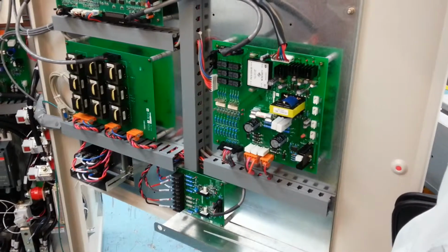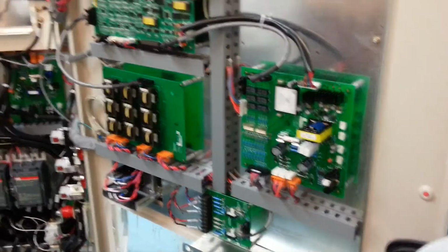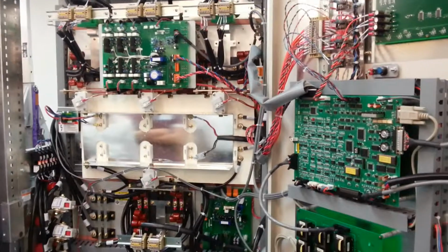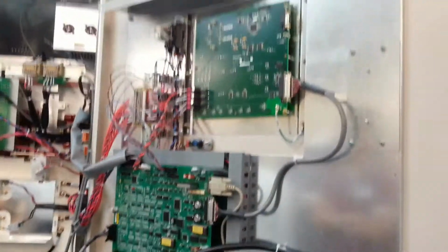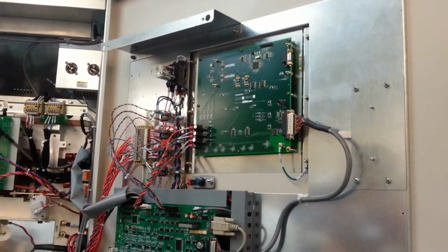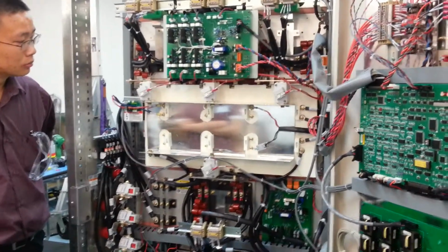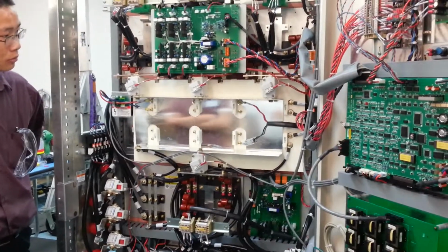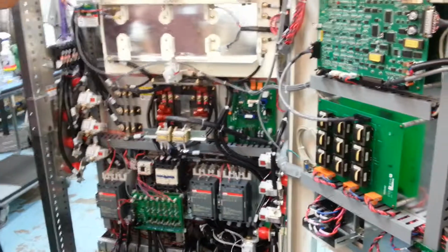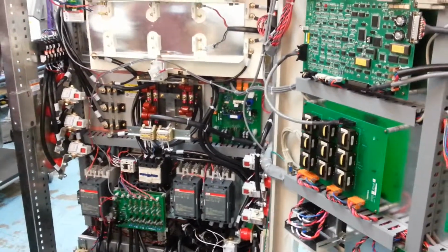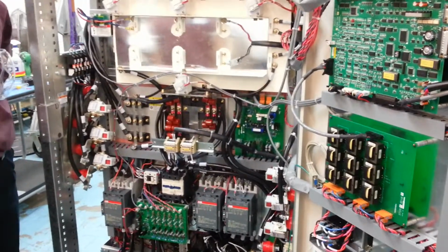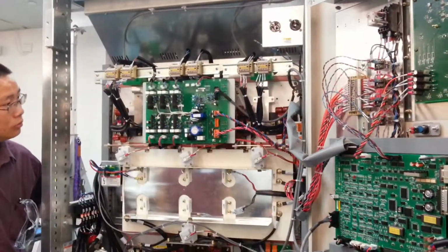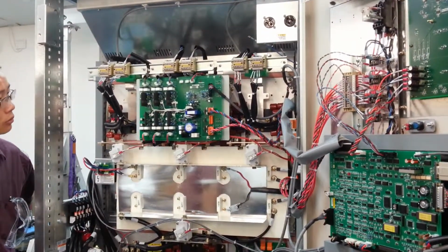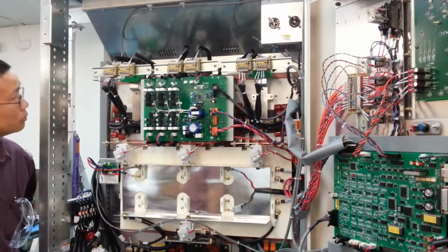Gets all your positive 5, your 15, your control. But then also the driver board makes its own for its IGBTs. So that way everything's isolated. So if you ever do have a failure, drives are the same way. The board produces its own positive, negative 15, which is your turn on and turn off for your switching devices. Minimum vendor usually is 12 to 13 volts, minimal. Usually 15 to 16 is pretty nice, but it produces its own. High voltage comes in, there's rectifiers on the front there, on the right before the cap, and there's your power supply right there. There's your flyback transformer for all your switching.